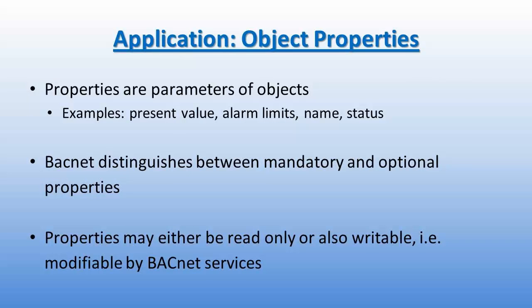Properties are parameters of objects. Some examples of properties would be the present value, alarm limits, name, and status. BACnet specifies 123 properties of objects. Three properties — object identifier, object name, and object type — must be present in every object.